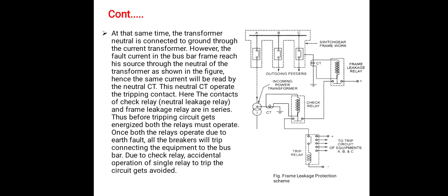When the fault occurs outside the protective zone — that is, an external fault condition — the earth leakage current will pass through only the earthed secondary of the power transformer and the check relay contacts will close, but not the frame leakage relay contacts. Since only the check relay contacts close, the multi-contact relay will not operate. Fault bus protection is more favorable to indoor than to outdoor installations.